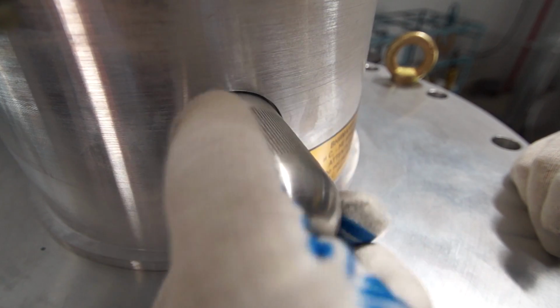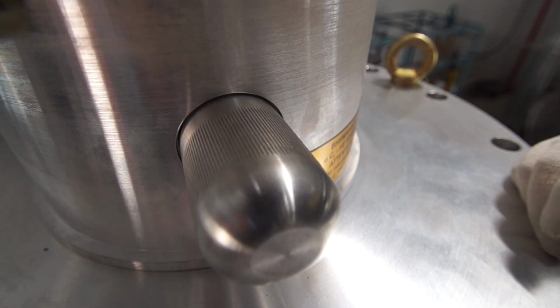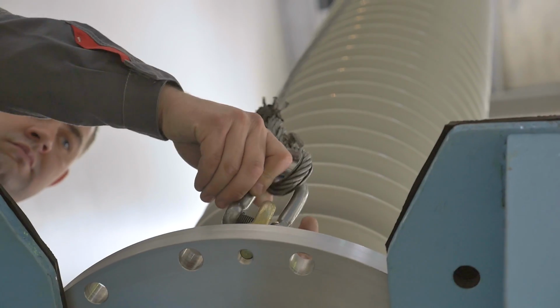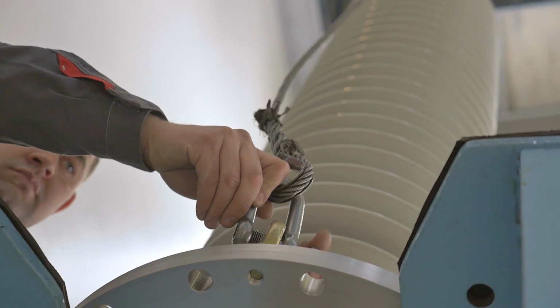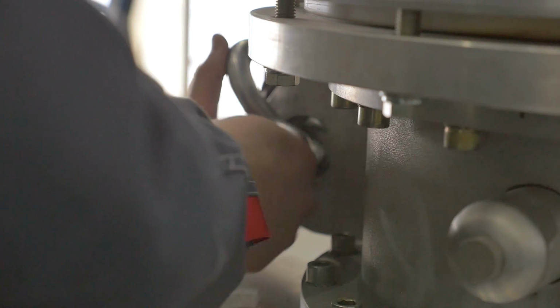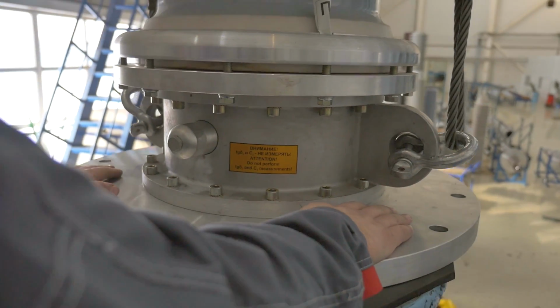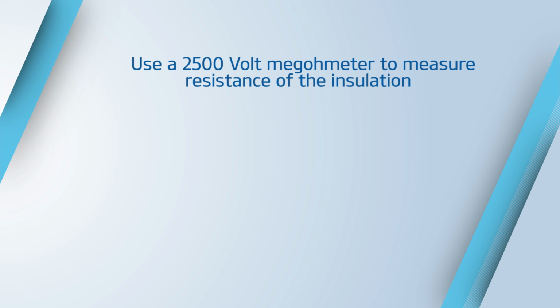Afterwards, it is required to screw on the hood of the test tap by hand by pressing on the rubber O-ring on the test tap body. The quick but demanding operation of the test tap grounding allows for eliminating one of the main causes of high-voltage bushing's damage. Thus we have checked the condition of the internal insulation of the bushing.